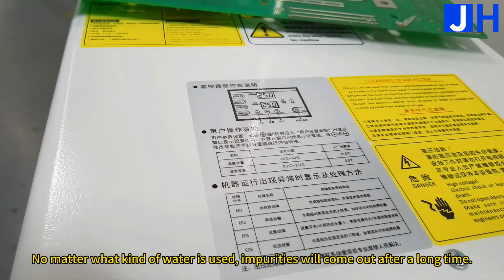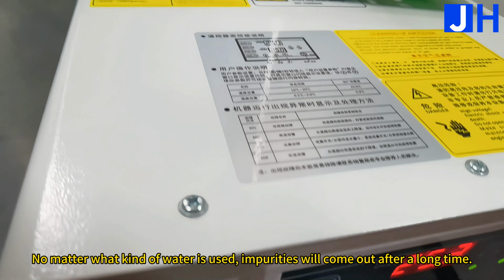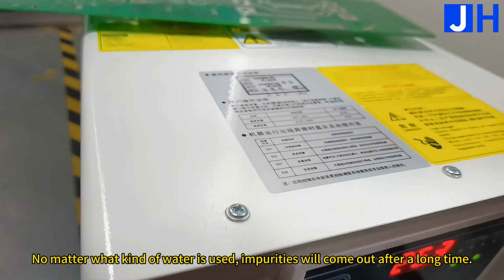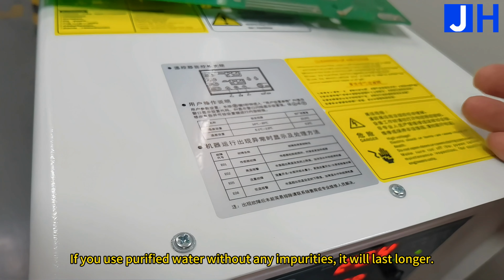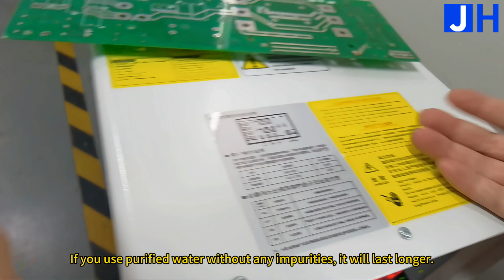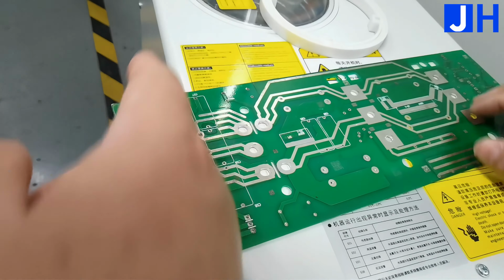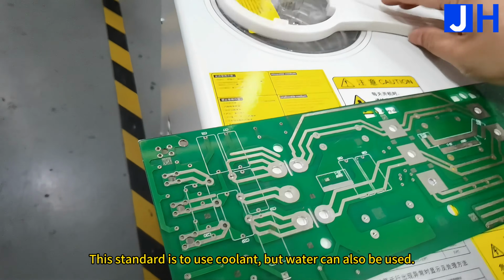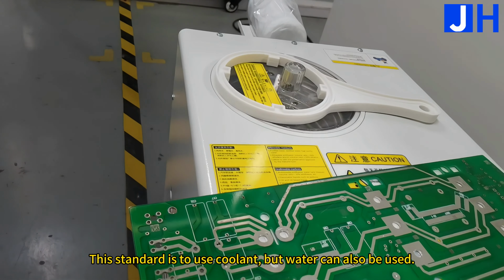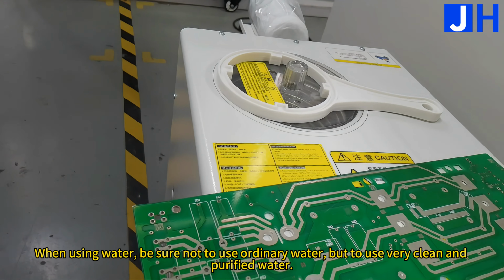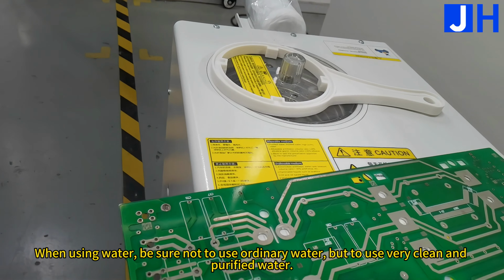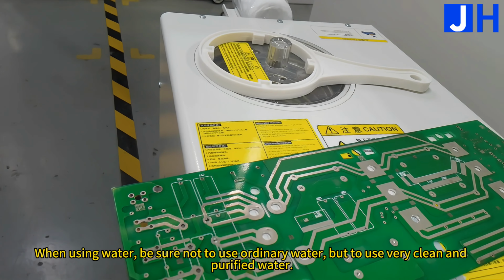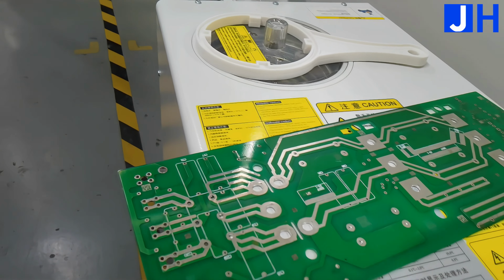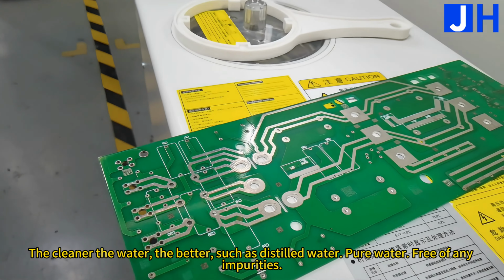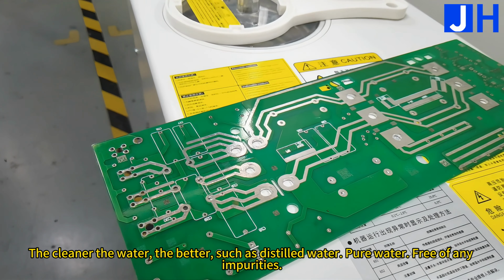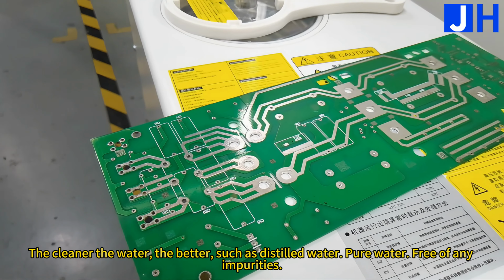No matter what kind of water is used, impurities will come out after a long time. If you use purified water without any impurities, it will last longer. The standard is to use coolant, but water can also be used. When using water, be sure not to use ordinary water, but to use very clean and purified water. The cleaner the water, the better, such as distilled water or pure water, free of any impurities.